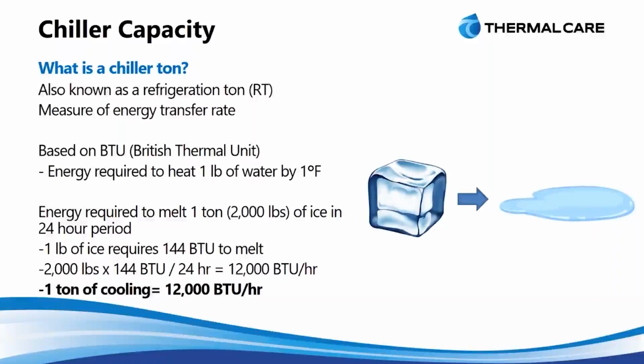And so it comes from a British thermal unit, a BTU. That's a measurement of energy to heat 1 pound of water to cause a 1 degree Fahrenheit increase in temperature. So to get to this chiller ton, we look at 2,000 pounds of ice, or a ton of ice, and how much energy it takes to melt that completely in 24 hours. What that boils down to is about 12,000 BTUs per hour. And so that's what we call a chiller ton.